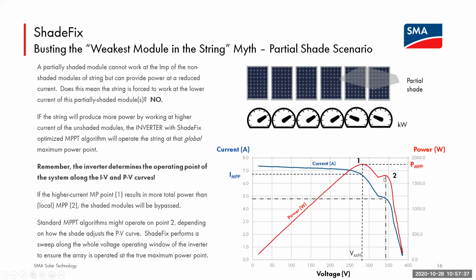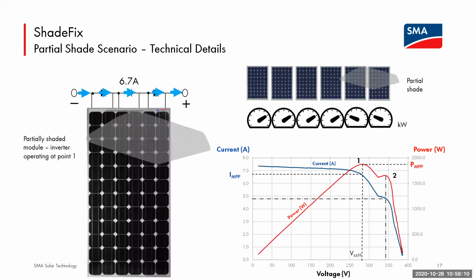And it allows us to really close the gap between what we provide automatically in our inverter versus what traditional optimizers provide. So that advantage that those optimizers used to provide when compared to old single MPPT, basic MPPT inverters is really minimized when we have this advanced MPPT ShadeFix algorithm. And you can see that here. Here's just a close-up of that diffuse irradiance or partial shade on this module.